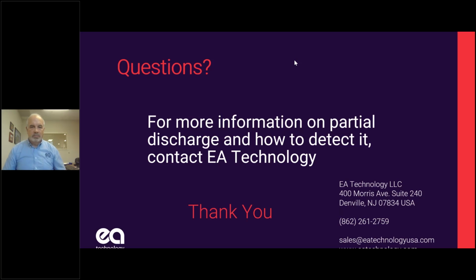Can PD inside a transformer be detected from the cables attached to it? Yeah, sometimes you can detect it. Sometimes you can also detect it with TEV or ultrasonic. For an oil-filled transformer, dissolved gas analysis is your best bet. It's much more sensitive than any electronic method. But putting the HFCT on the grounds of the cables or on the grounds of the transformer itself will detect it. But I don't think it'll detect it too far away. I don't think you can go to the far end of the cable.